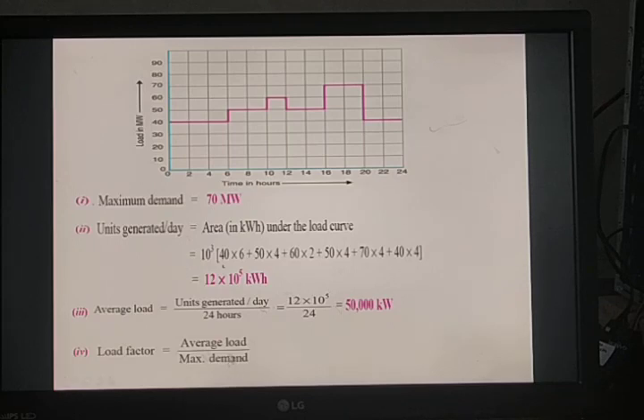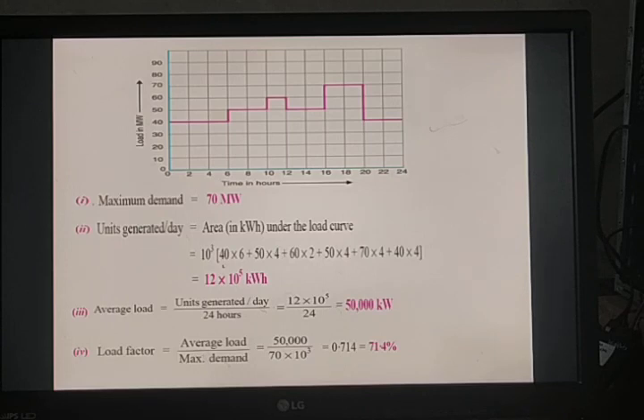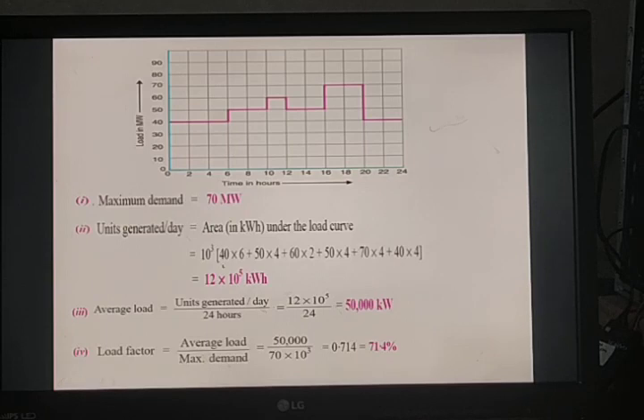Load factor = average load / maximum demand = 50,000 / (70 × 10³) = 0.714, or 71.4%. Summary: maximum demand = 70 MW, units generated per day = 12 × 10⁵ kWh, average load = 50,000 kW, load factor = 71.4%.